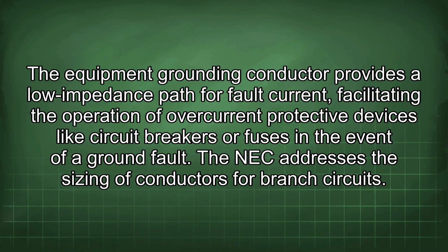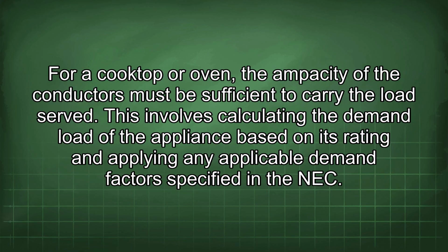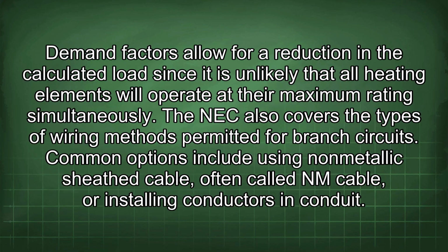The NEC addresses the sizing of conductors for branch circuits. For a cooktop or oven, the ampacity of the conductors must be sufficient to carry the load served. This involves calculating the demand load of the appliance based on its rating and applying any applicable demand factors specified in the NEC. Demand factors allow for a reduction in the calculated load since it is unlikely that all heating elements will operate at their maximum rating simultaneously.